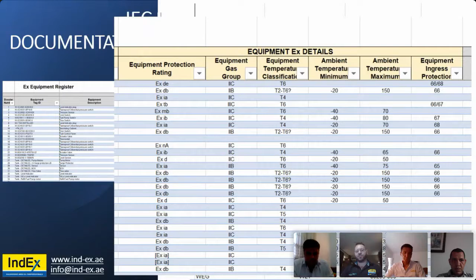First thing you do is, you have all your equipment individually tagged with a unique tag. You then define what the description is and where it is installed, when the inspection happened, and to what grade of inspection: detailed, close, or visual. You have the equipment details from the manufacturer, model number, and serial number. You then have all the Ex details: protection, gas group, temperature class, ambient temperature range, IP rating.